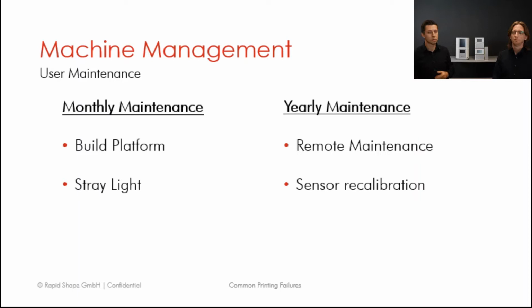And last but not least, which is something we talked about a little bit but not in detail, is the yearly maintenance. The yearly maintenance is the remote maintenance and the sensor recalibration. Both of them are included in the remote maintenance contract, which is free for the first year with the rapidshape machine. The remote maintenance is done by rapidshape, so by us. We will check through the machine once a year, check everything, and check if updates can be done and so on. Additionally, there's the sensor recalibration, which is quite important as the sensor is calibrating the power you are printing with. If the sensor is outdated, you might not get the real estimated power, the power we used for the material parameters, but less or more, which then also leads to unexpected results.